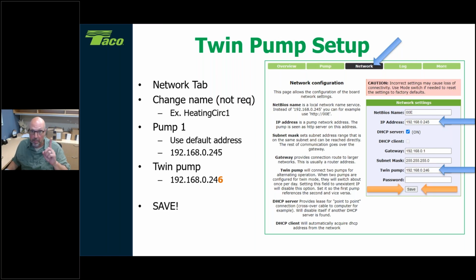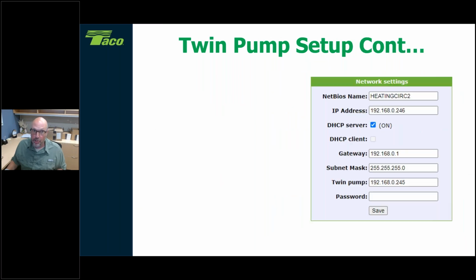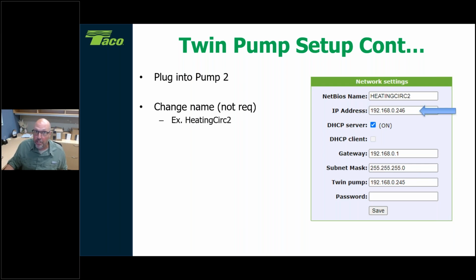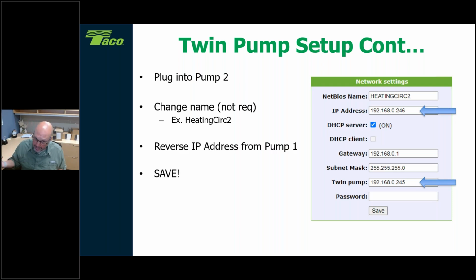Now you're plugged into pump number one. Now what you have to do is take your Cat 5 out, go into pump number two, and change the IP address of that one to 246 now. So the default, that was 245, you're changing to 246. And then you come down to the twin pump mode, and it will be blank, and you're going to have to type in 192.168.0.245. So this way it knows to go back to that one. And then, of course, hit save. Remember to hit save.